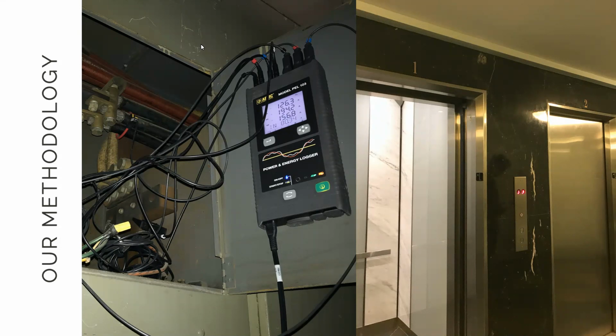Now, what kind of results did we get from this data logger deployment? The building's common area loads consume an average of about 2,000 kilowatt hours per day under normal conditions. To completely meet that daily need during a grid outage, you'd need quite a large battery. So our proposed solution here is not actually to deploy a 2+ megawatt hour battery, since the building is limited in space and budget, but rather to find as good a compromise as possible between the battery's usefulness during backup operations and its cost effectiveness during day-to-day operations.